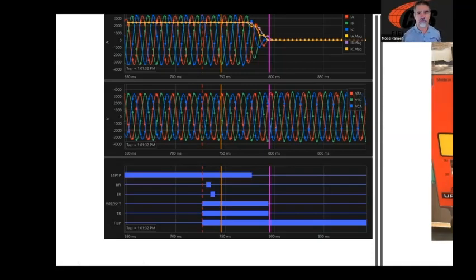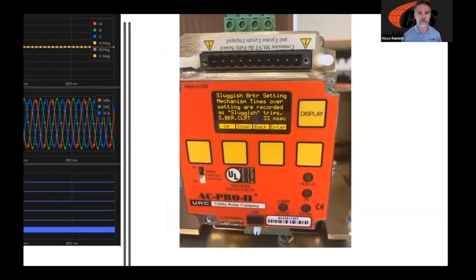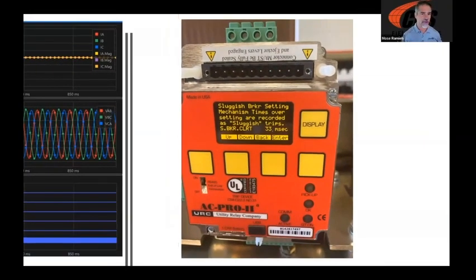Well, what about my folks with low voltage breakers, right? What about you guys that have those low voltage substations? What about you? Timing first trip testing of a low voltage breaker is a little bit more complicated. There is a product out there that we're working on that can do first trip testing of breakers using vibration. But there's also manufacturers like the AC Pro 2 here, made by Utility Relay Company, that has a sluggish breaker feature. And that sluggish breaker feature allows you to know, hey, in the event of a fault, did my breaker trip as fast as I was expecting it to?